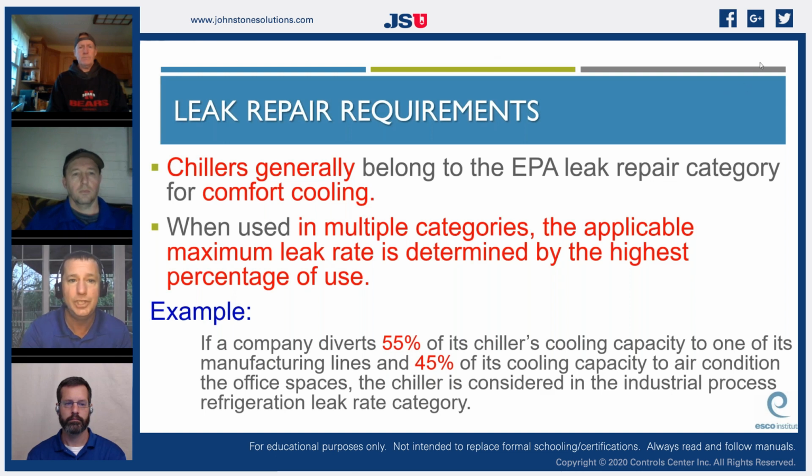So chillers generally belong to the EPA leak repair category of comfort cooling, because a lot of these chillers are being used for, you know, large buildings. And so they're primarily used for comfort cooling. When used in multiple categories, the applicable maximum leak rate is determined by the highest percentage of use.